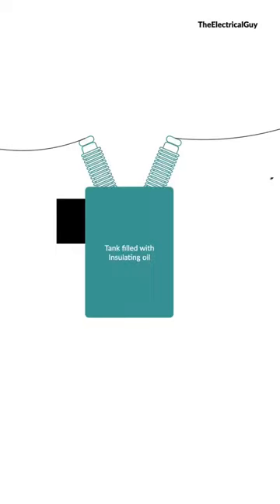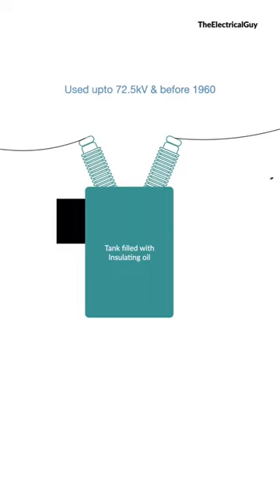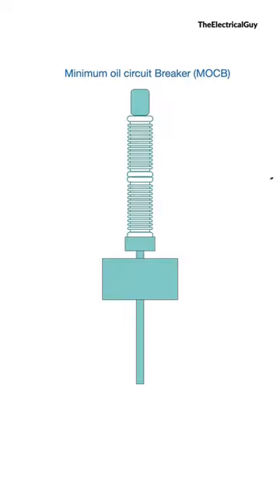Oil circuit breakers are composed of a steel tank which is filled with insulating oil completely. The breaker contacts separate and the current interruption takes place within the tank filled with insulating oil. This type of tank arrangement was used only up to 72.5 kV and before the 1960s.